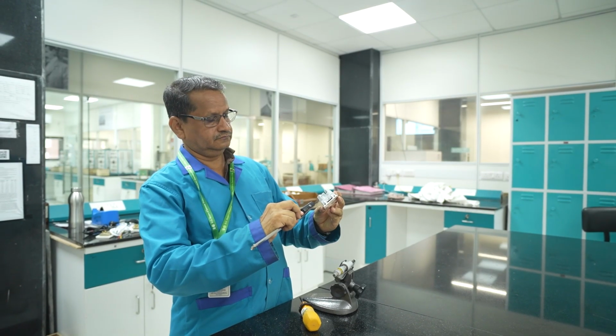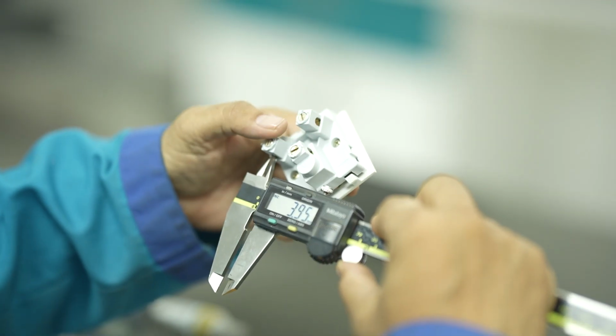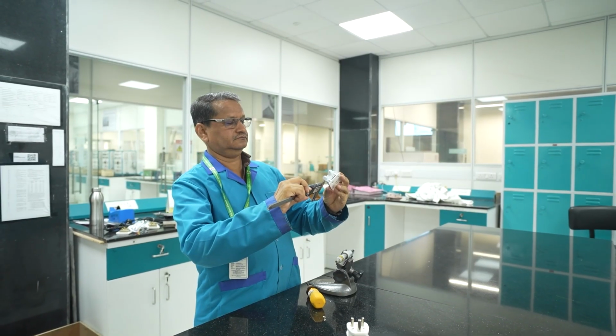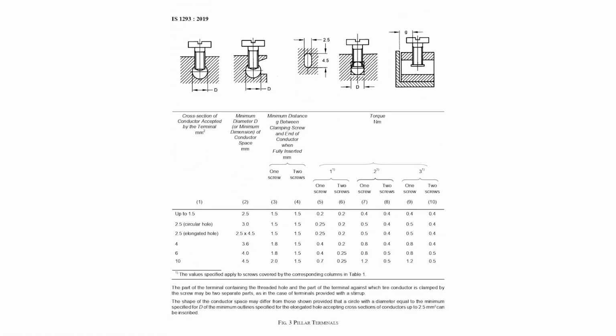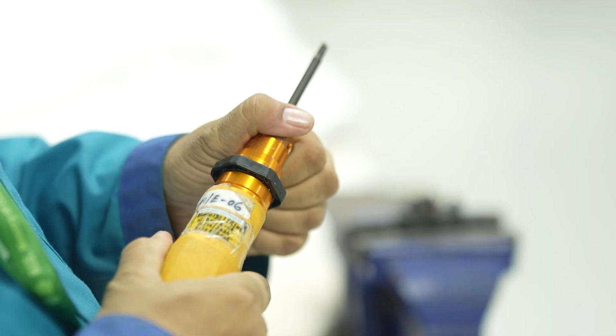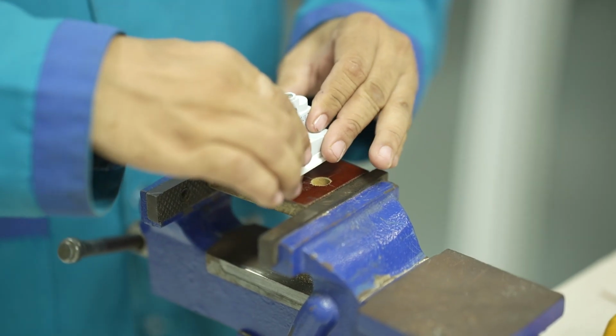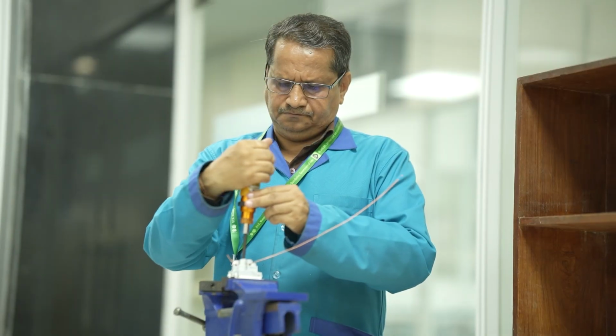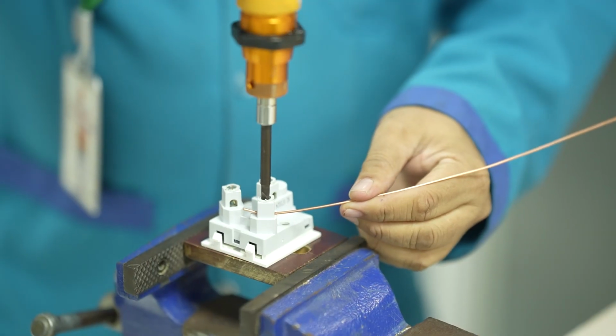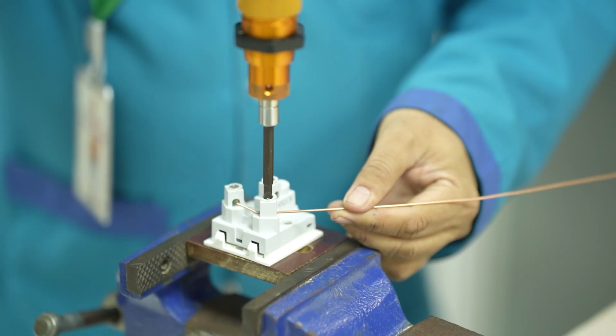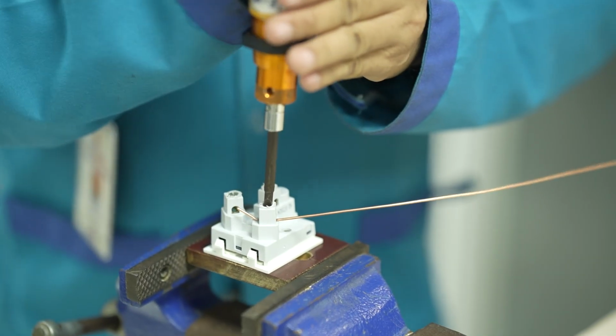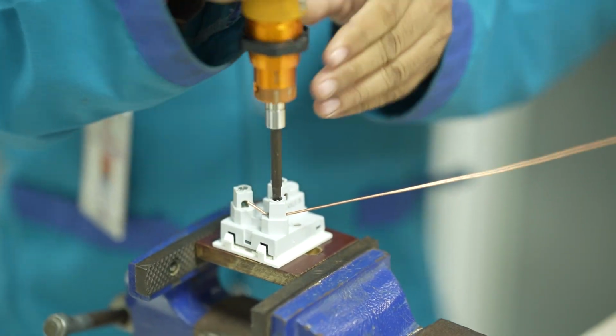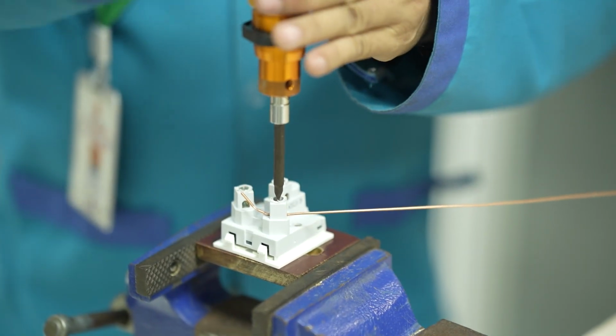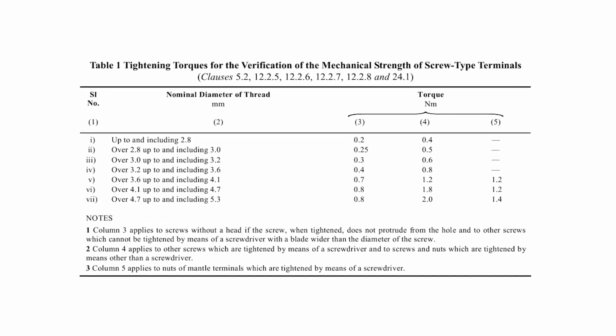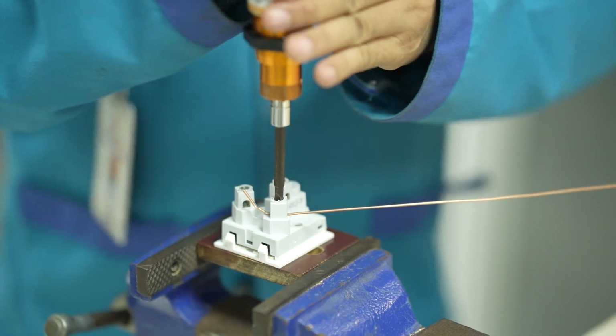Terminals. Clause 12. The minimum conductor space requirement is verified as per the accessory rating. Conductor space must meet requirements specified in Figure 2 to 4 of IS 1293. Terminal strength is assessed using torque. Screw clamping terminals must remain secure when screws or nuts are tightened or loosened. Compliance is checked by inspection and testing with the largest rigid copper conductor per table 4. Screws are tightened and loosened 5 times using the torque specified in table 1 of figure 2 to 4. No loosening or damage is allowed.